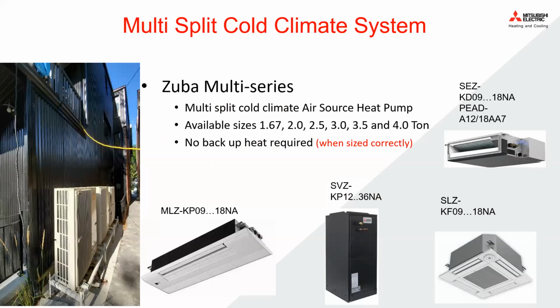Now, when you're designing or building a multi-level home, a multi-split system is actually a wise choice for occupancy comfort. With the central system, you have a single thermostat, and how are you supposed to satisfy the temperature requirements for level one and level three at the same time? With a multiple split system, each indoor unit has an independently controlled thermostat, and you can set your system up anywhere from 2 to 8 zones. The little picture on the side here is a home in downtown Toronto where they set up 3 multiple split systems. Each space has multiple heads inside that they can zone out.